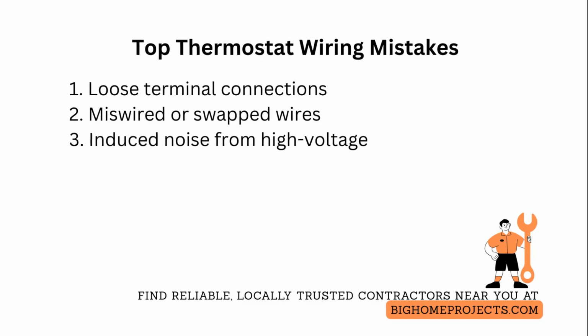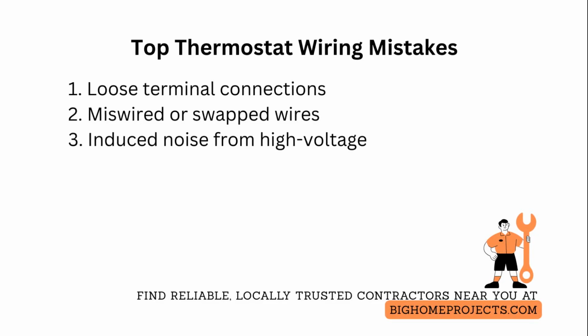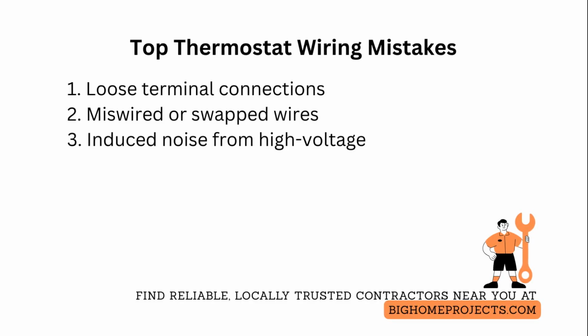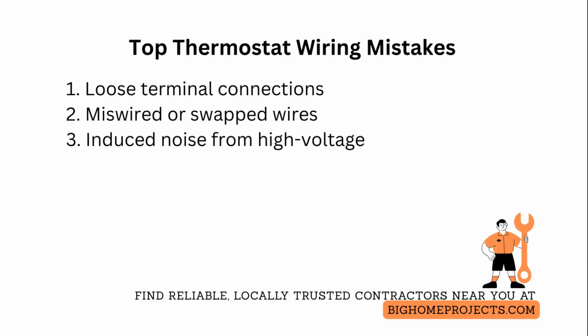Second is miswiring or swapped wires, creating wrong mode operation and short cycles. Solve by labeling wires at removal, consulting the wiring diagram, and confirming terminal identity with a continuity test.